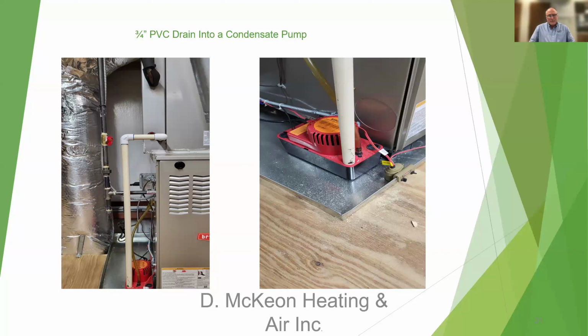If you notice, the slide on the right has an emergency drain pan. That is typical in an area that would be in an attic or even in a basement or in a closet, wherever your furnace is located. Just in case you do have a condensate drain issue, the emergency drain pan there holds the water. And in the front of the pump there, you'll see two red wires going down to a float switch. That float switch will stop water from going over the pan and flooding the rest of the room or the ceiling in the attic or the basement, whichever it is.